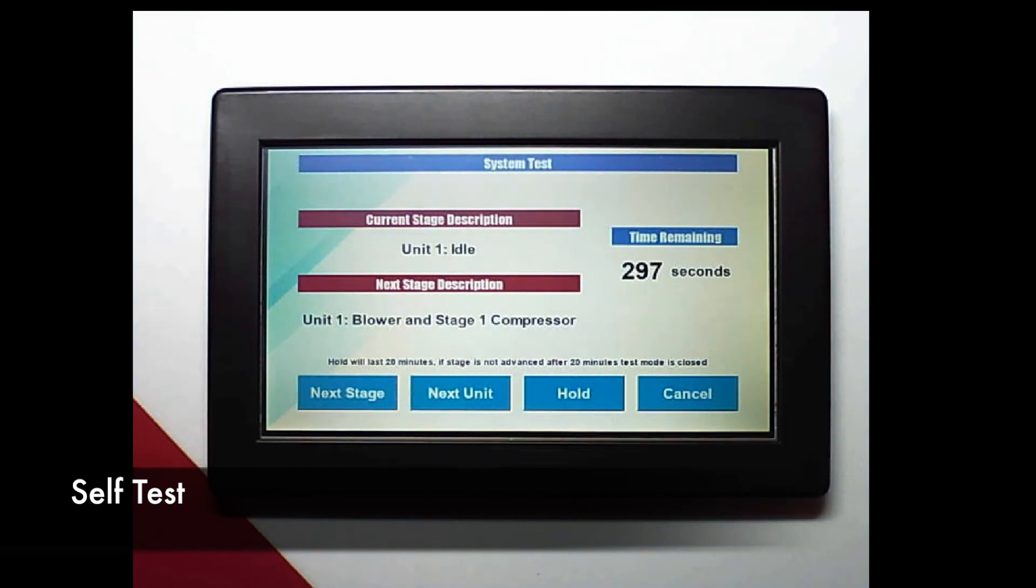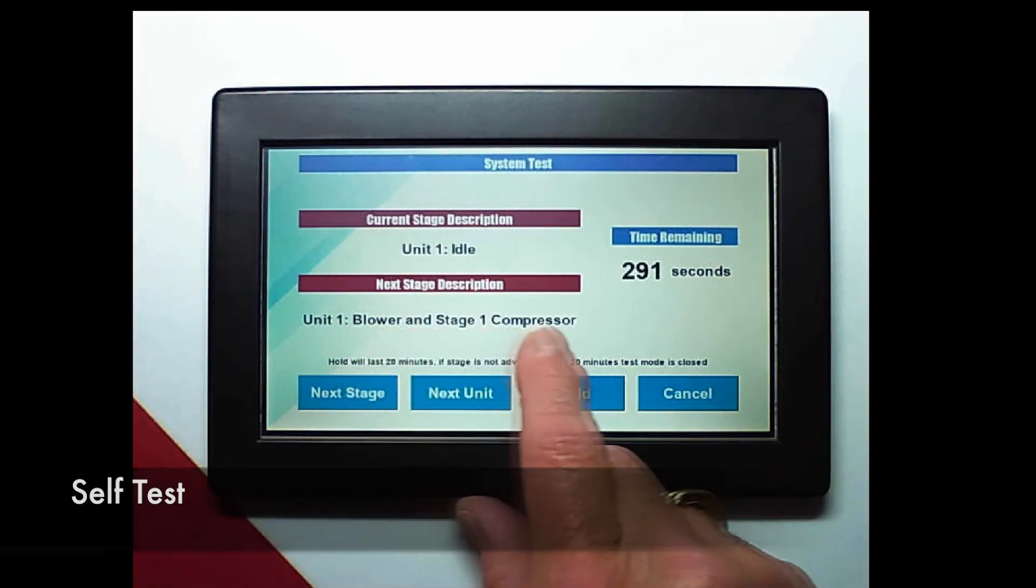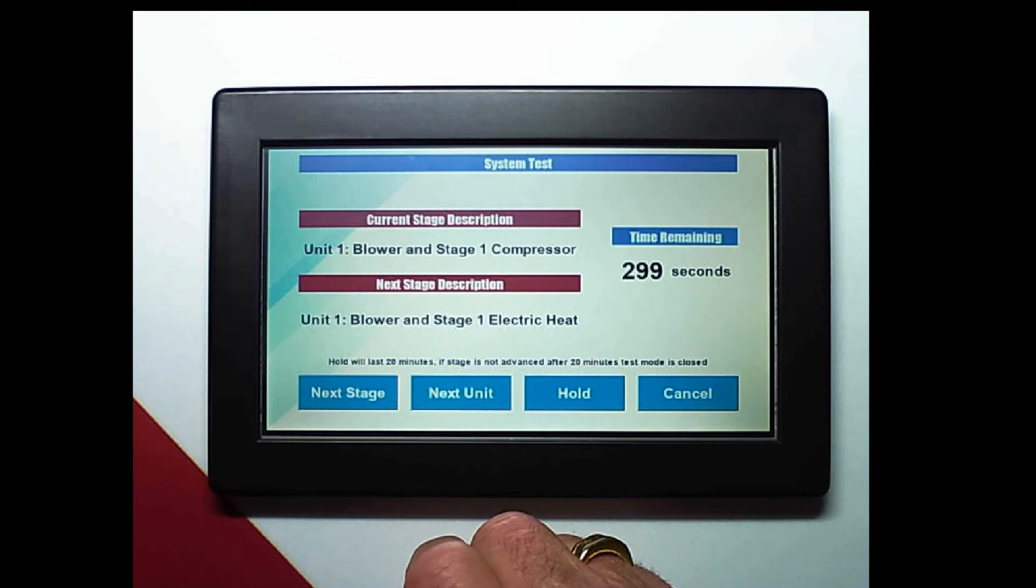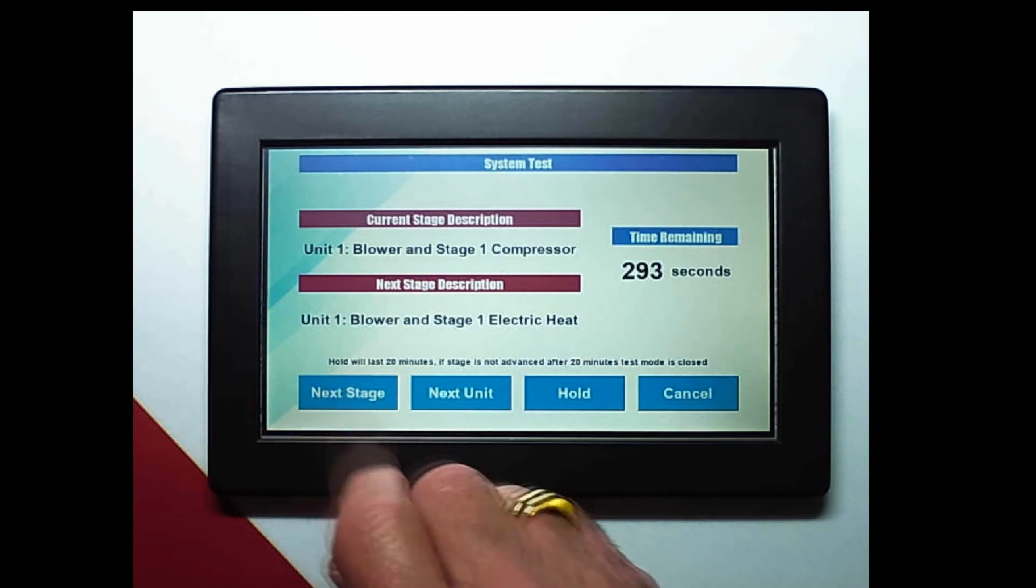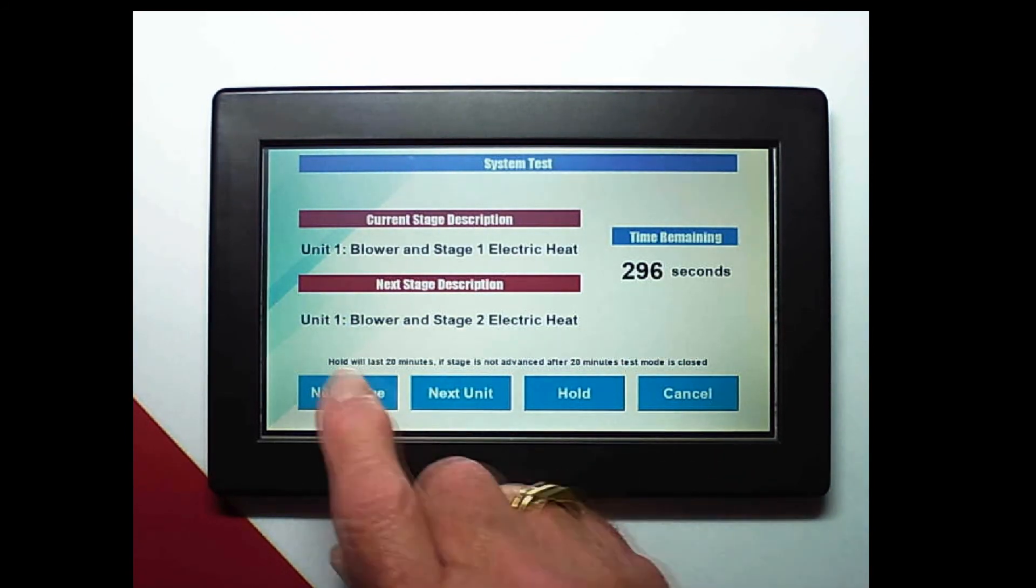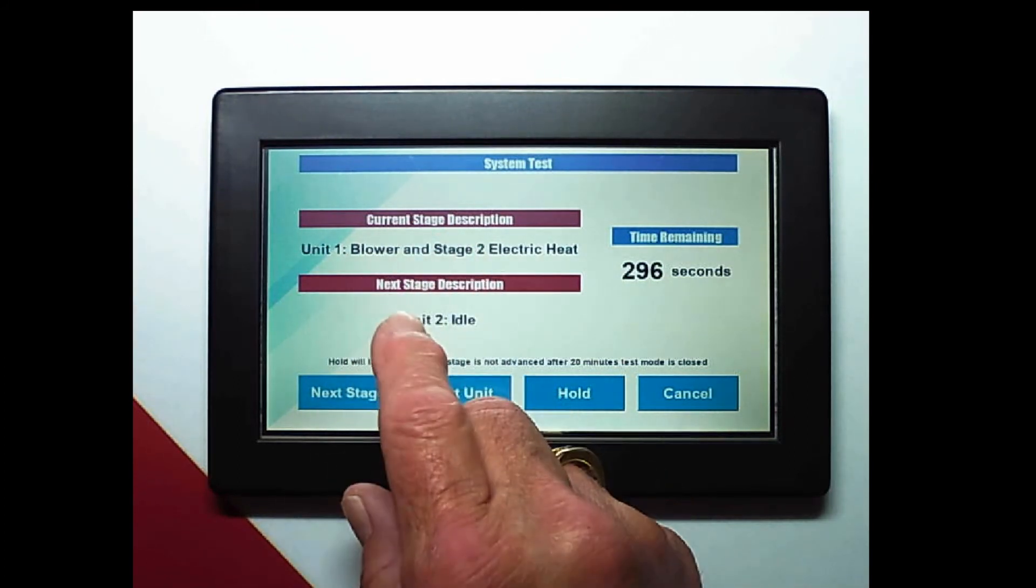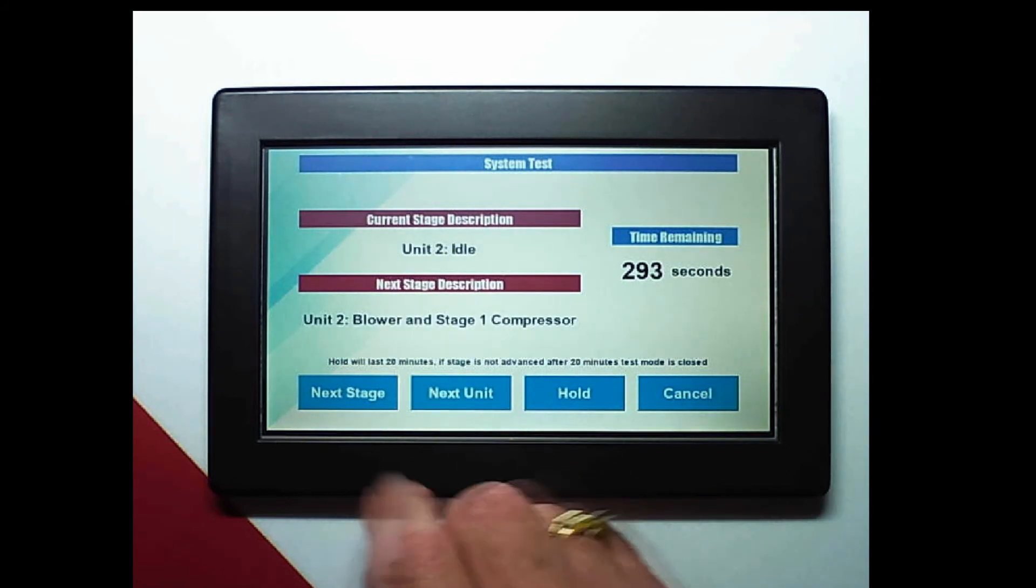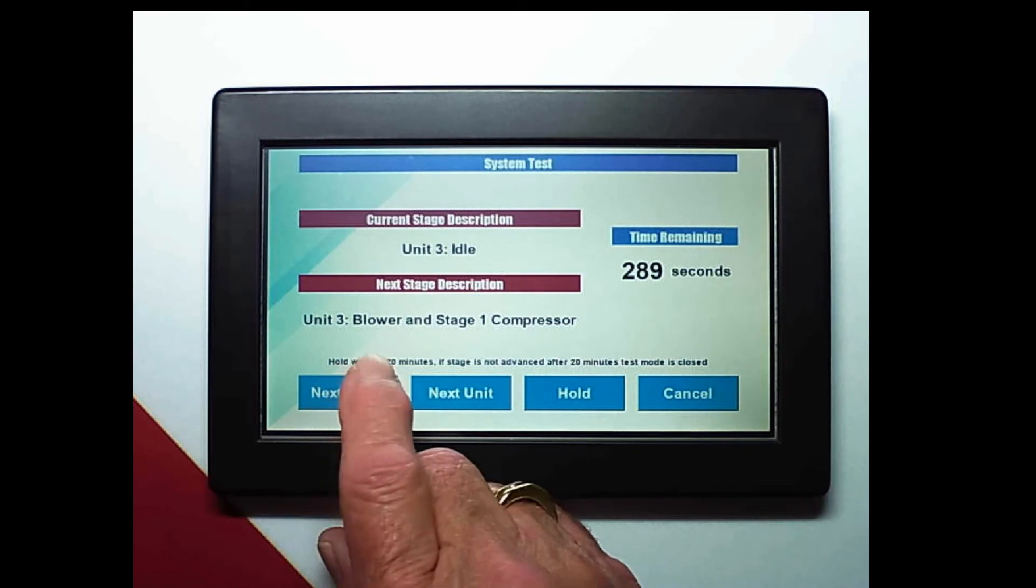For the self test it gives me 300 seconds per stage and it will automatically run through that or I can click next stage in the lower left corner or next unit and advance that. If I needed to check something out if I'm suspicious that something isn't functioning properly I can push the hold and it will give me 20 minutes, it will give me 1200 seconds. And then I can switch to next unit and get 300 seconds again or cancel the entire process.